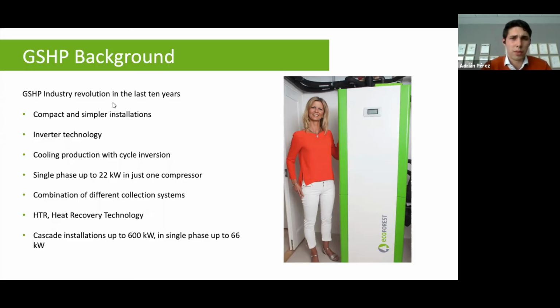Our bet was to make our installations compact and simple. For that reason, we bet on inverter technology in ground source heat pumps, a technology already used in air source heat pumps at that time, but not in ground source. We also included the possibility to do cycle inversion in the unit. We introduced units up to 22 kilowatts in single phase. We have one model called EcoGeo 522, with one compressor that modulates from 5 kilowatts up to 22 in single phase. In fact, there's the option to make a cascade up to 66 kilowatts with this unit.